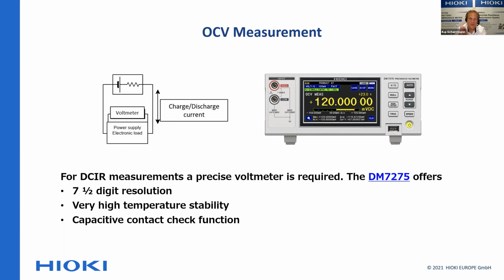A lot of people use a standard DMM from one of the large manufacturers. HIOKI has a DVM, just a voltmeter, ideal for these open circuit voltage measurements in the DCIR process. The nice thing about this one is it's not 6.5 digits like the standard DMM, but 7.5 digits resolution, and it has very high temperature stability.